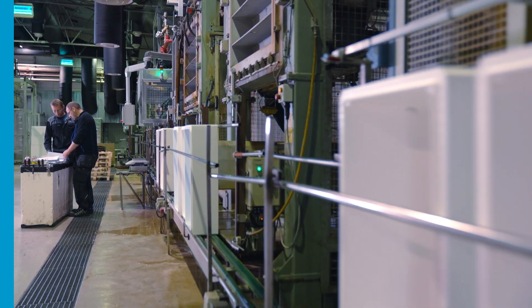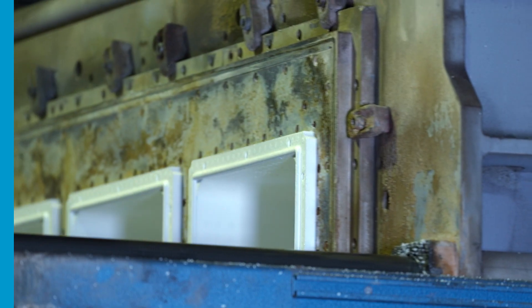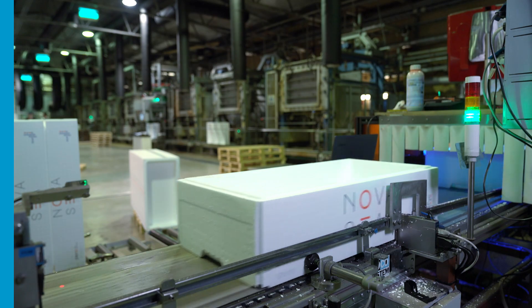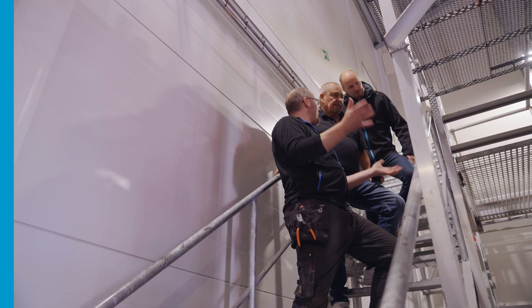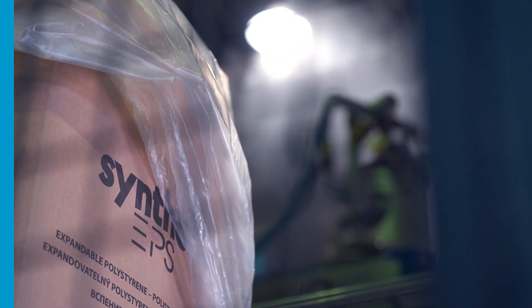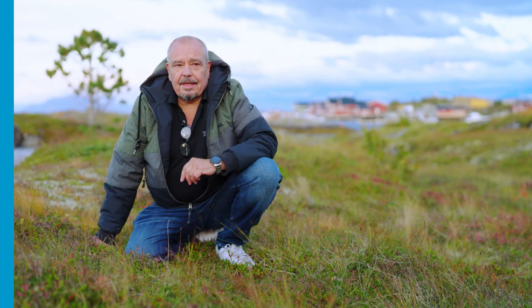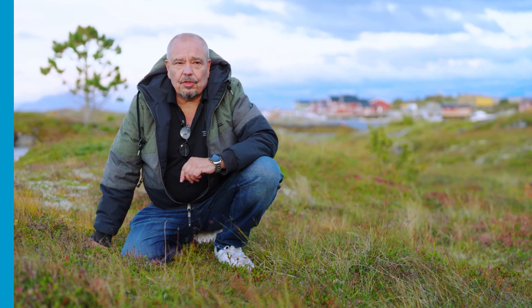A reliable vacuum supply is critical to Atlantic Styro's production process — no EPS without LRP. Producing expanded polystyrene is a hot and humid process, and we need vacuum to evacuate the steam that's used. Liquid ring pumps are the ideal solution for this application. Liquid ring technology relies on water. The steam coming from the EPS production process is no problem — on the contrary, when it condenses, it is absorbed as part of the pump's operation.